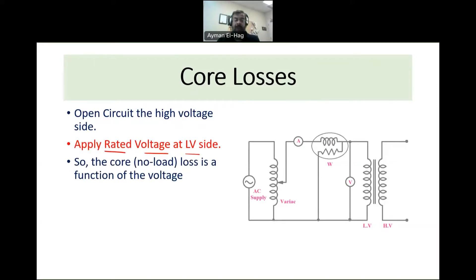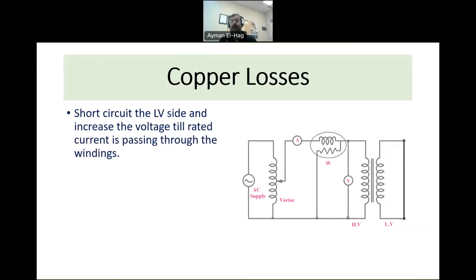So the core loss of the transformer is a function of the voltage. Now let's go to the copper loss. How we measure the copper loss? We short circuit the low voltage side, apply a voltage at the high voltage side so that we will have the rated current going through the winding. So this loss is actually a function of the current.